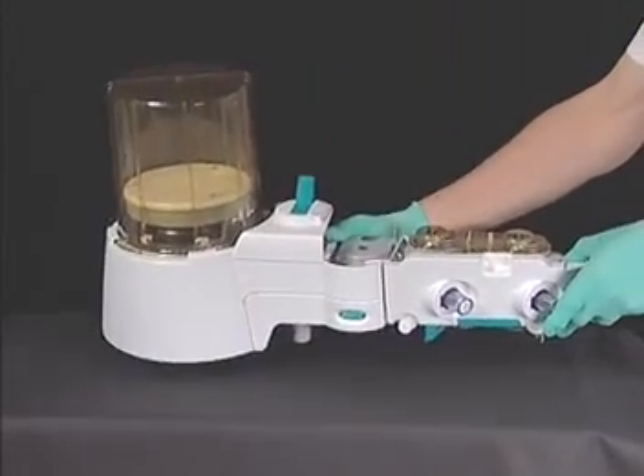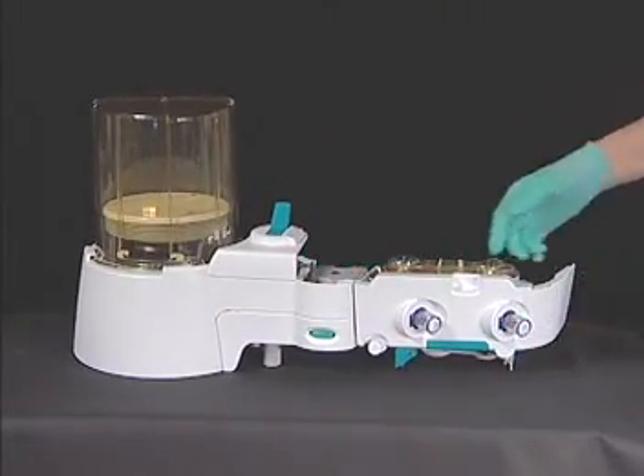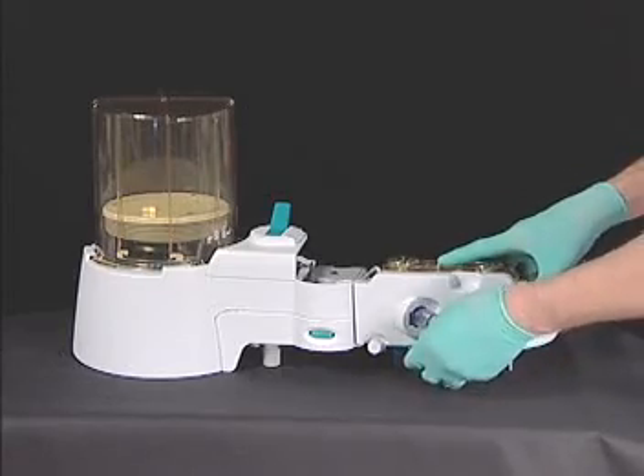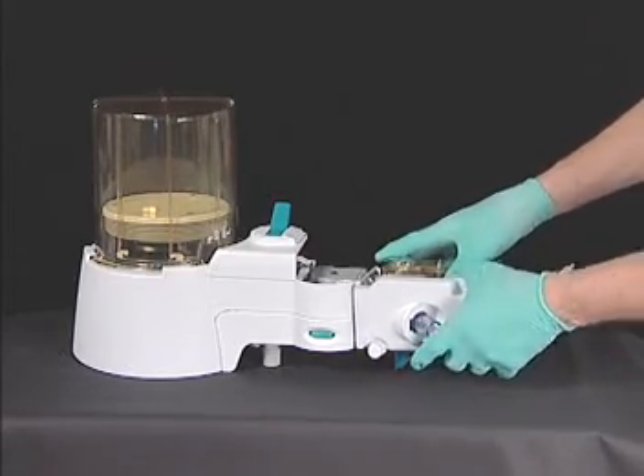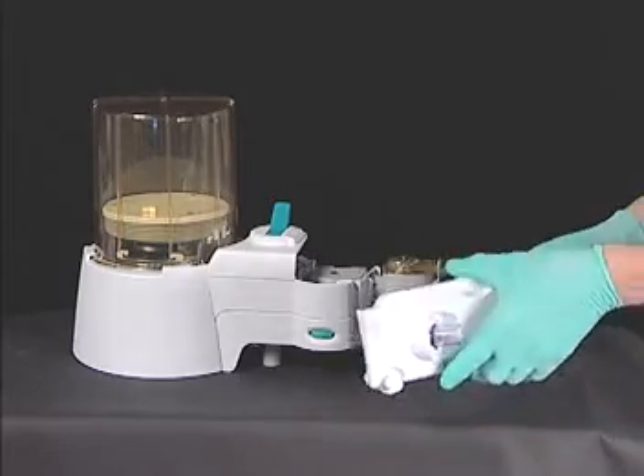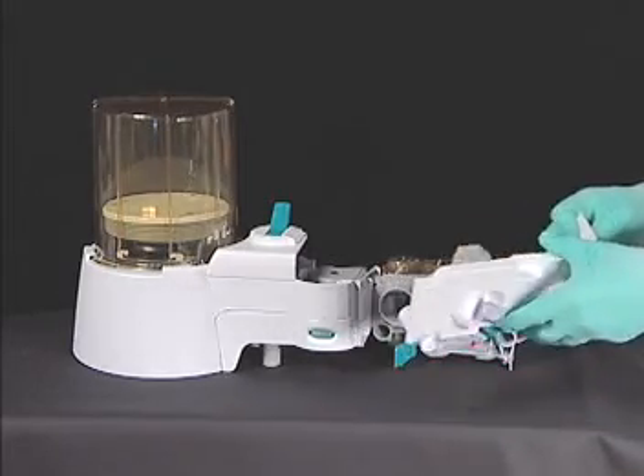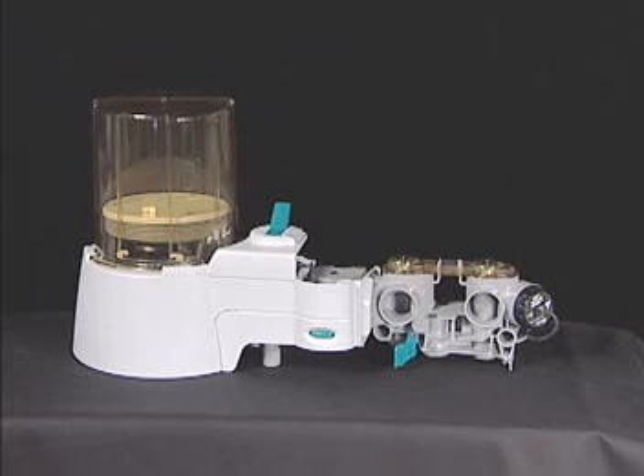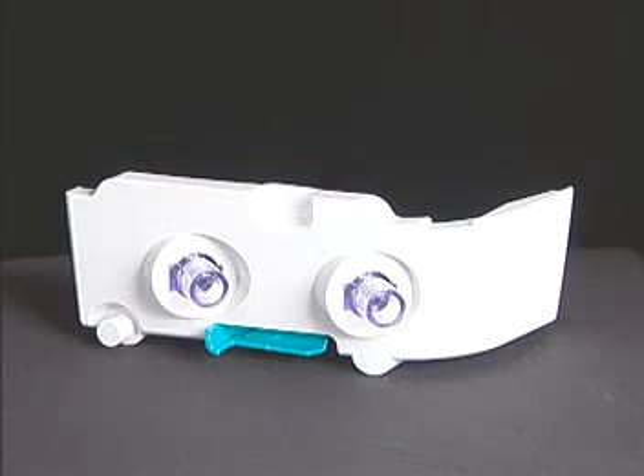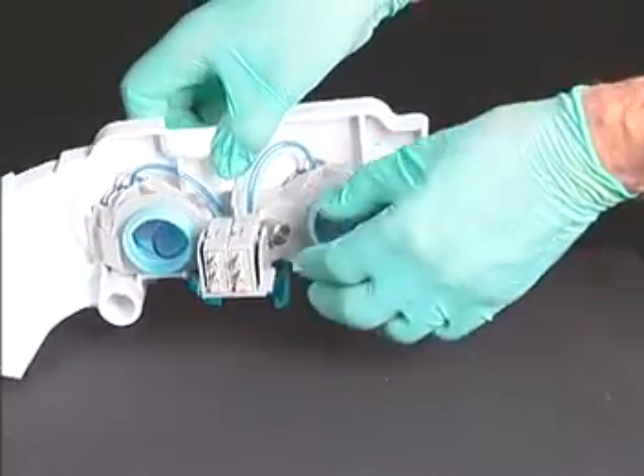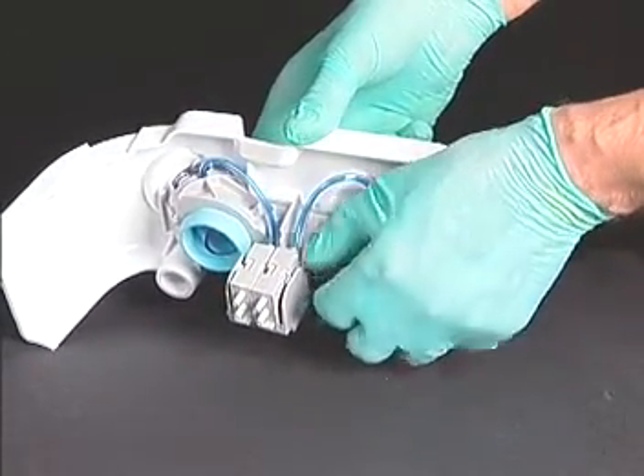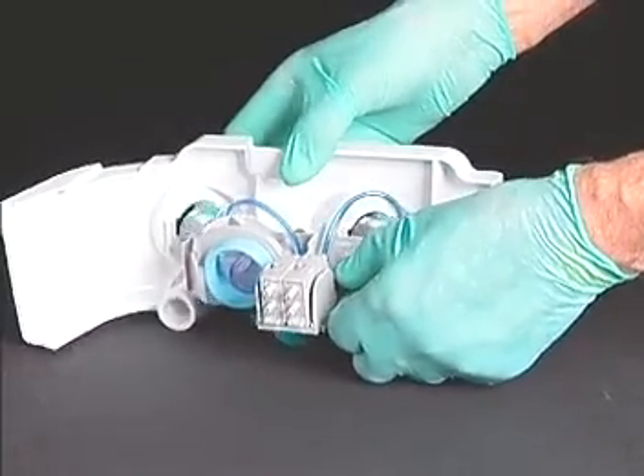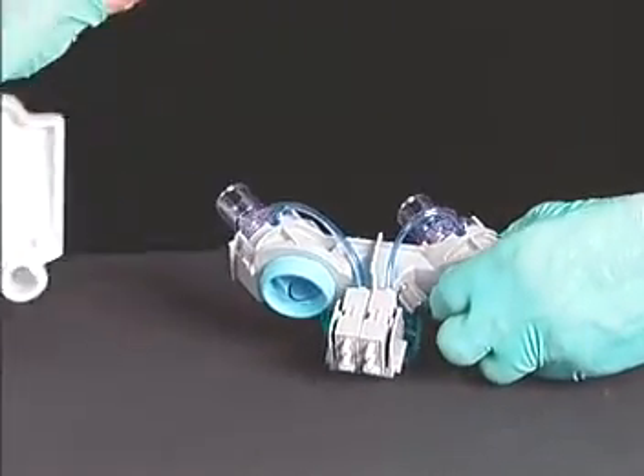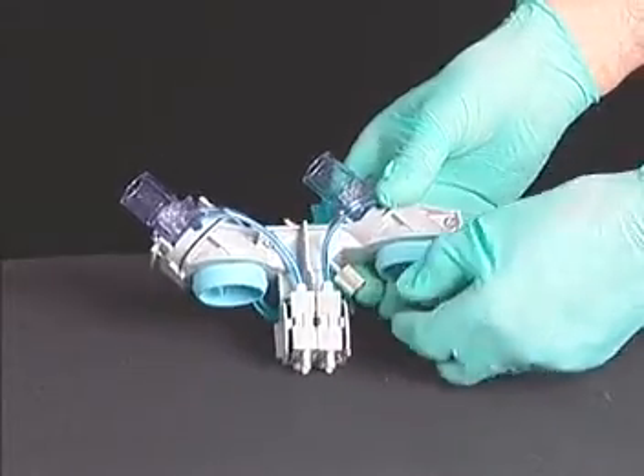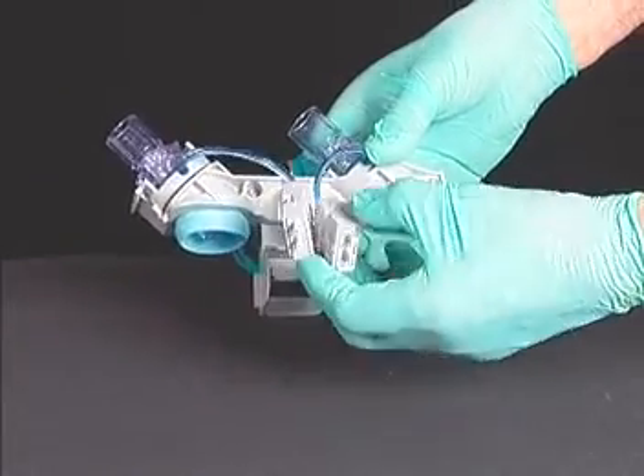When you are ready to disassemble the ABS, follow these steps. First, remove the flow sensor module by releasing the green lever and pulling the module away from the ABS. Some resistance is normal because the flow sensors are overcoming the seals required to maintain a leak-tight breathing system. Then, loosening the thumb screw allows you to separate the flow sensor holder from the cover. Once the holder has been separated, you can remove the flow sensors for cleaning or replacement without tools.